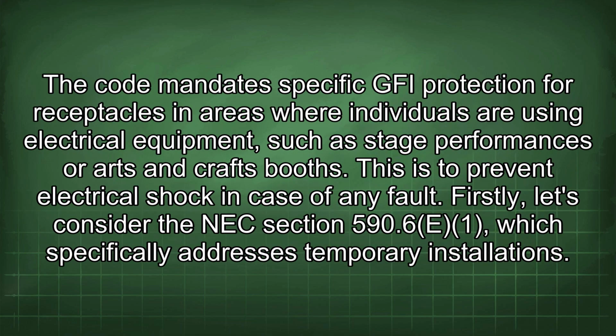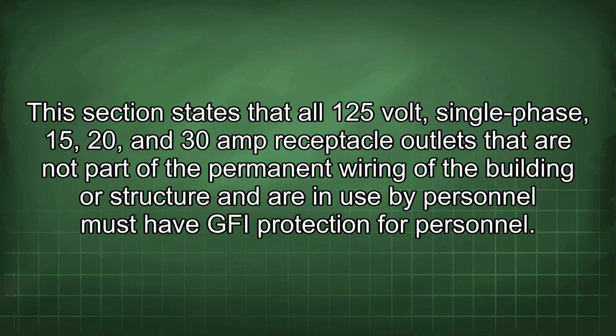The code mandates specific GFI protection for receptacles in areas where individuals are using electrical equipment, such as stage performances or arts and crafts booths. This is to prevent electrical shock in case of any fault. Firstly, let's consider NEC section 590.6(A)(1), which specifically addresses temporary installations. This section states that all 125-volt, single-phase, 15-, 20-, and 30-amp receptacle outlets that are not part of the permanent wiring of the building or structure and are in use by personnel must have GFI protection for personnel.